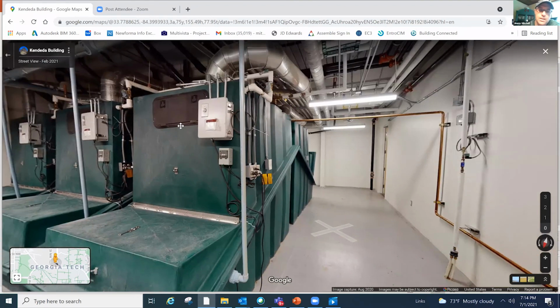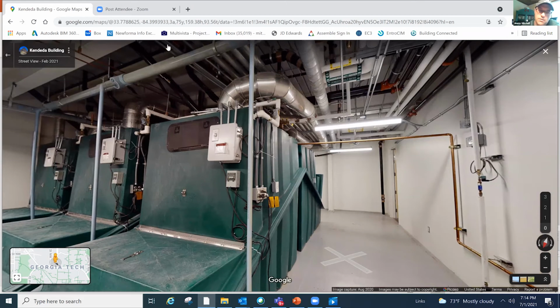The one interesting thing is that from the water closet, the pipe is essentially an exhaust duct - it's pressurized, and air will flow through the pipe, through the stainless steel exhaust, and out through the roof through an exhaust riser. That's actually an impactful design change, because in a regular building I'd never suggest a waterless urinal - I'd always say a 1/8 gallon urinal, since that flow of water really helps with odor. But in this scenario, with the restrooms under negative pressure and always being sucked out, waterless urinals work great here. There's no odor problems since it's always under negative pressure. Of course, if that exhaust fan ever goes out, the building stinks up in about 10 minutes.